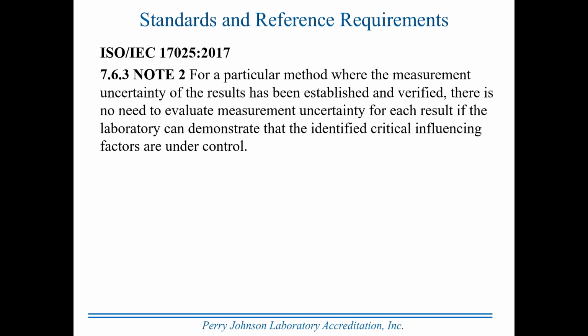typically this is talking about statistical control, SPC, for instance, statistical process control. If you can determine that the significant contributors are under control statistically, then you don't have to estimate uncertainty every time you perform the test. You can estimate it under carefully controlled conditions with all the significant contributors being able to be proven to be in control, and apply that uncertainty to that test every time you perform it. Now, obviously, if the test changes dramatically, different equipment introduced or something of that nature, this would not apply. But as long as you're doing the same test, using the same equipment, following the same procedure, this does apply.